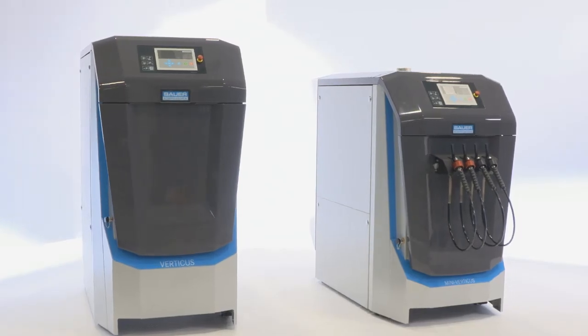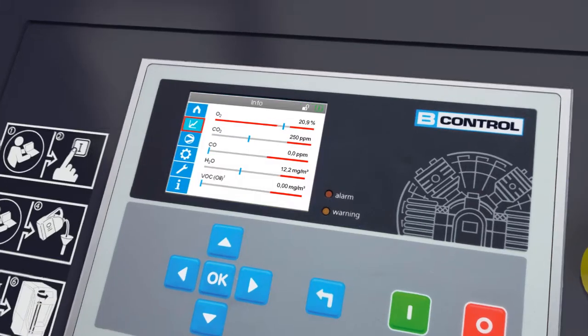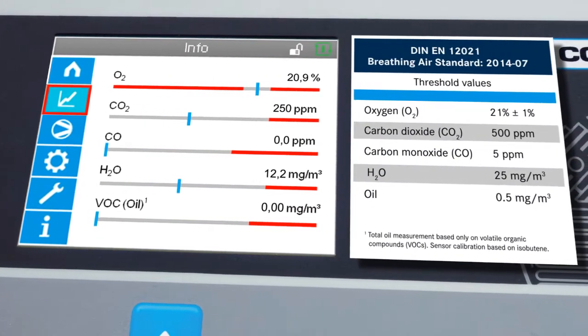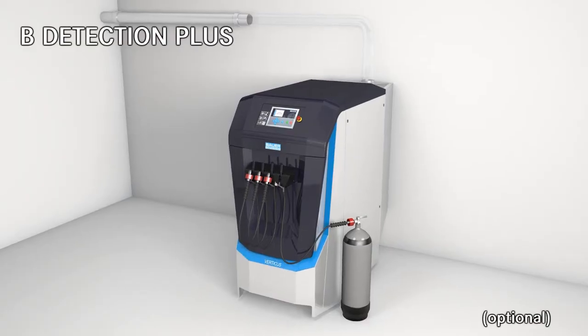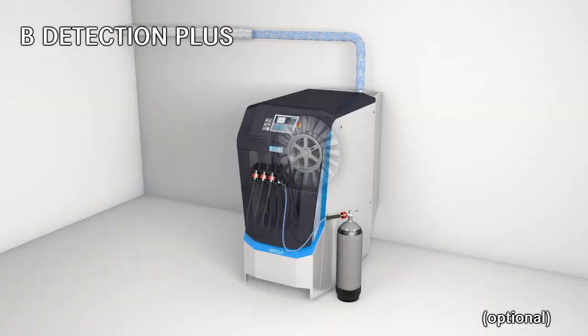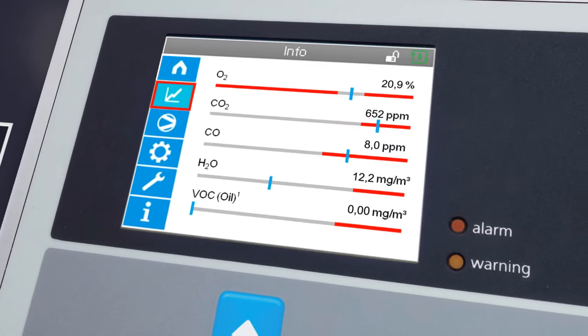Verticus stands for safety and security — safety where the health of your customers is involved, and security in liability issues. We guarantee compliance with all statutory limit values for breathing air, including carbon monoxide and dioxide, moisture and oil. The gas measurement system monitors the air for these critical levels. If limits are briefly exceeded, the flush valve discharges the air to the outside. If limit values are exceeded for longer, the Verticus displays an alarm and automatically shuts down.